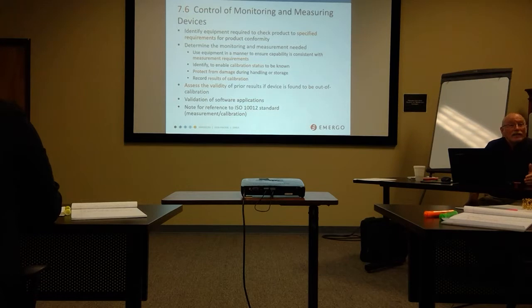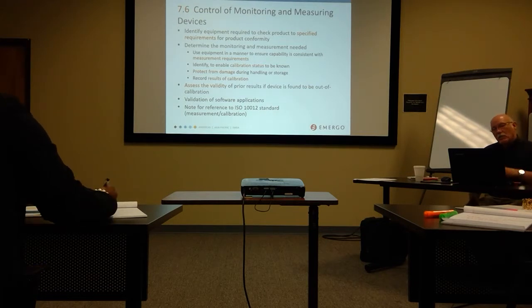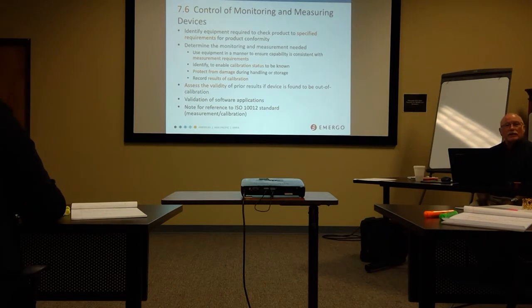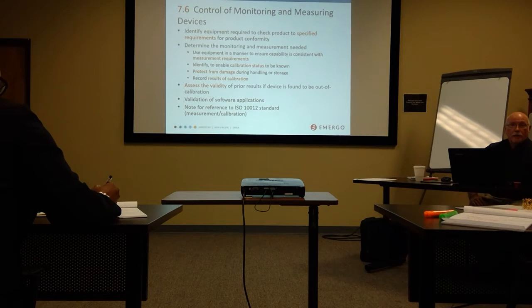So what could this mean? Hopefully it doesn't mean much. It's not that big a deal. Potentially it could be very serious, could end up in a massive recall and all kinds of ugliness. A lot of people don't pay that much attention to this process. It's critically important, and I would have in your procedure that when those calibration certs come back from the vendor, someone, I would recommend QA, review them and sign off on them to make sure that somebody's looking at these things.